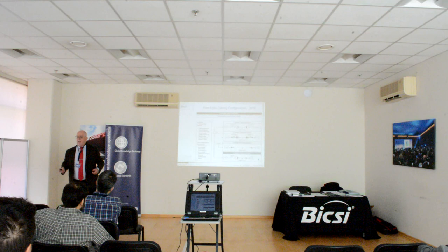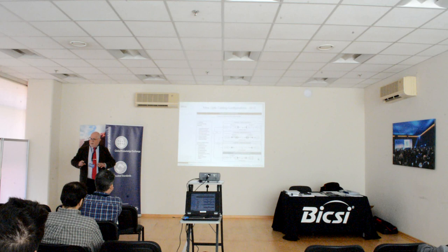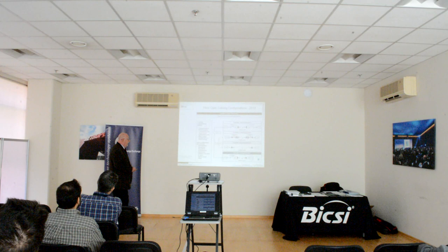It's a troubleshooting test. It's a test to do if something is failing, not working. You can use the cords that are attaching the panel to the equipment. You use those cords in the test method. It's a very accurate test method, but it's only valid for the equipment cords that you've got. If you change the equipment cords, all the results are different. That is the only change to the configurations that has happened since 1987. So 32 years we've had the same test configurations, and recently we've had this extra one put in. And it's a good decision to make that extra one, but as I say, it's really only a troubleshooting test.